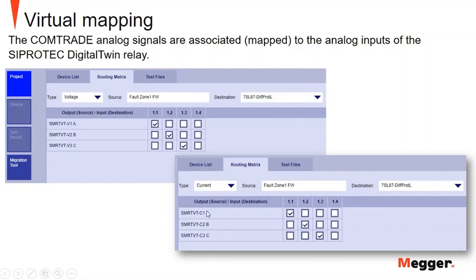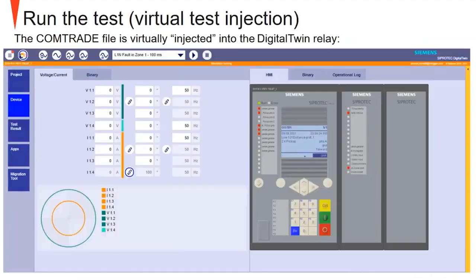Also, we connect the current generators of the test set, which are ComTrade signals in A, B, and C, into the current transformer signals 1, 2 and 3 of the relay. So we are connecting virtually the test set to the relay. And then we tell the environment to run this information into the relay, so play.